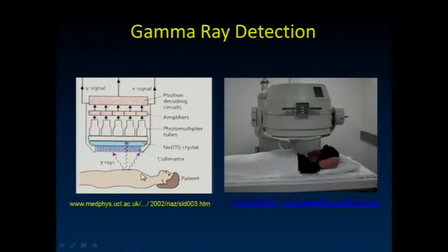So here's that gamma camera. On the front, we have this collimator, and I've made the analogy to the grid. The difference here is, how do we get an image in focus in radiographic imaging? Well, we use a point source of radiation. The radiation all comes from the point source in the X-ray tube, and so therefore the image is in focus.